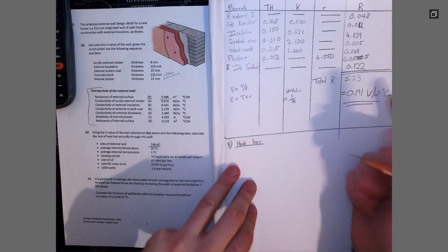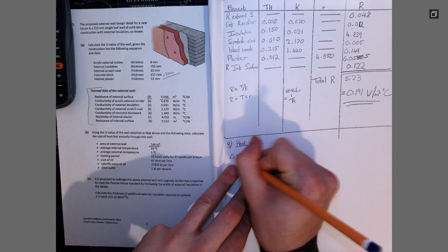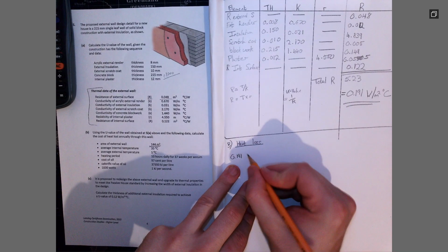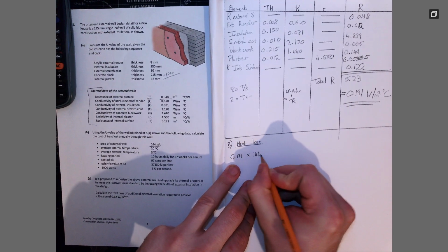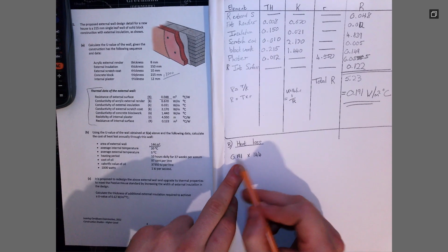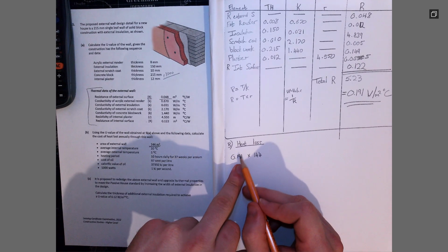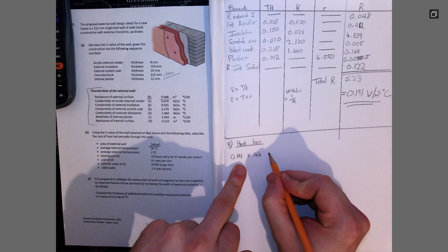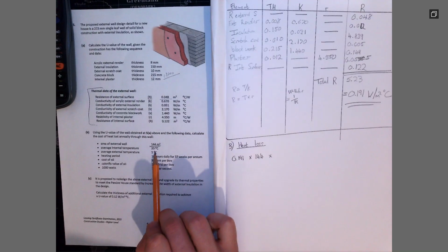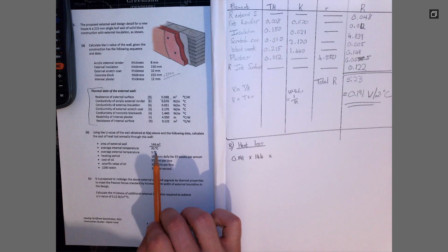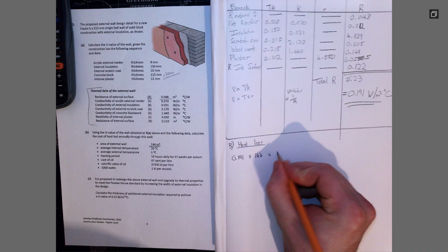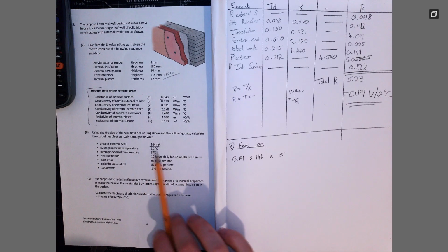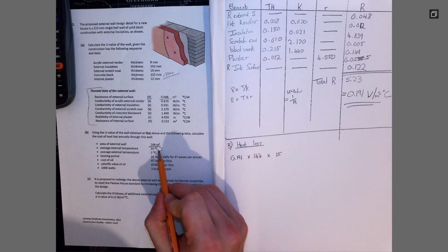To do that, we use our U value, in this case 0.191. What we then do is multiply that by our area. If this is given for one individual spot, this is the total size that's going out through. What we then have to look at is what's called a temperature difference, which is over on this side. In this case, it's 20 minus 5, which is going to be 15. That means that if inside is about 20 degrees and outside is about 5 degrees, the heat will naturally want to go outside.